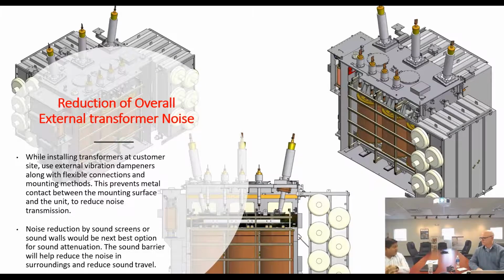So Brad, you gave a perfect example for reducing the overall external transformer noise. Using a sound barrier or sound wall is the basic next option for containing the sound within the perimeter and reducing the attenuation to the outside perimeter. And that's what you have seen mainly on the interstates and highways: if you have a residential or commercial area nearby, there is a sound barrier which will reduce the sound spreading through that particular wall and going to the nearby vicinity. Another way of reducing the transformer noise at the site is to use vibration dampers underneath the transformer. The vibration damper will help to reduce the transmission of the transformer noise to the transformer pad and to the whole surrounding structure. So outside the structure, there are mainly 2 ways of doing it, and that's how we can contain the sound level at certain limits that have been designed.